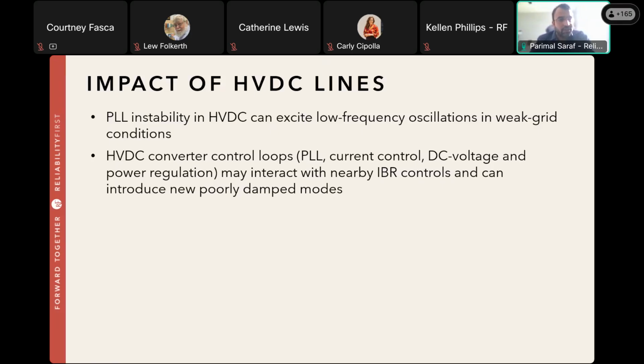And as has been discussed for IBRs in the previous slide, PLLs under weak grid conditions can excite low frequency oscillations in the system. Also, HVDC controls can interact with nearby IBR controls if they are in a region that has a significant IBR penetration, and can introduce new poorly damped oscillatory modes. HVDC lines also have demonstrated converter-driven impedance resonance-based oscillatory behavior in a lot of offshore wind farms.